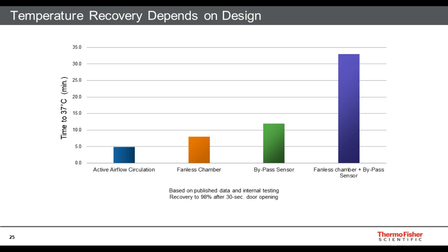So with that in mind, let's look at how recovery of temperature after a door opening can vary depending on the design of the incubator. So what I'm showing here is a table showing recovery to 37 degrees, or 98% of 37 degrees, after a 30-second door opening. So the inner and outer door of the incubator was open for 30 seconds. And this is a common test for functional performance of an incubator. So left to right, the small blue bar shows recovery in 5 minutes after a 30-second door opening, and this is an incubator with a circulating fan and a temperature probe located in the incubator chamber.